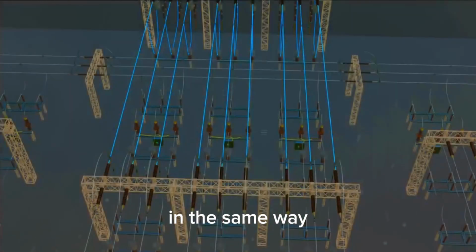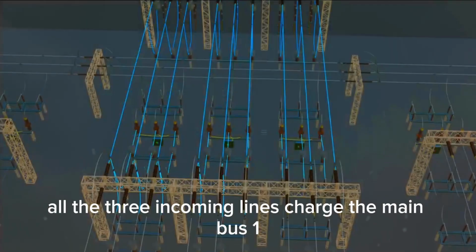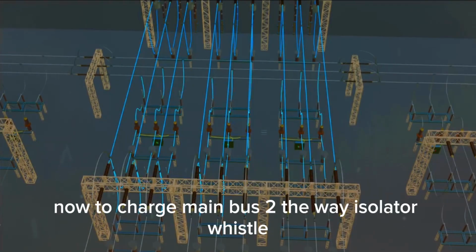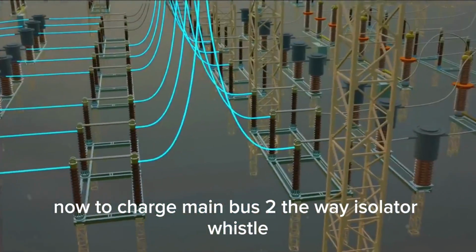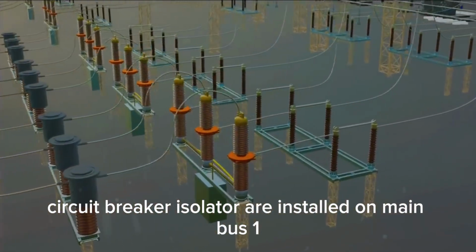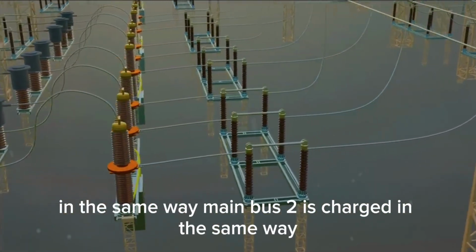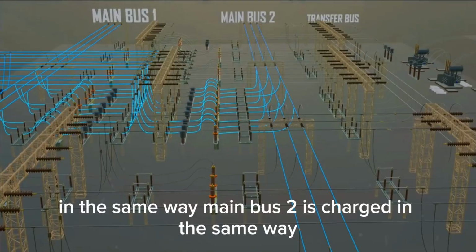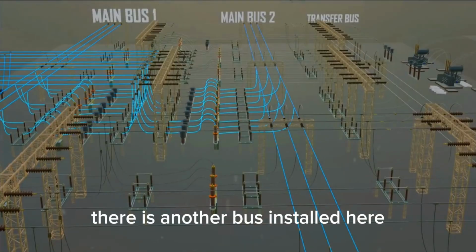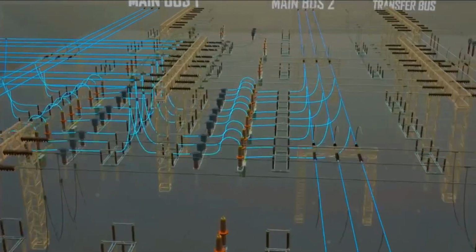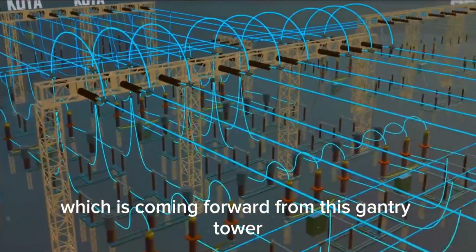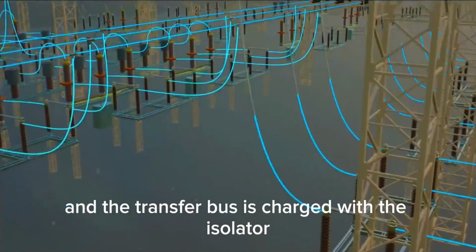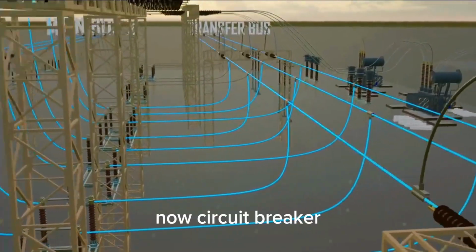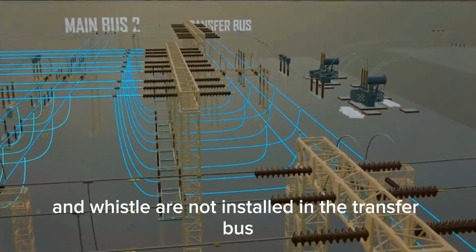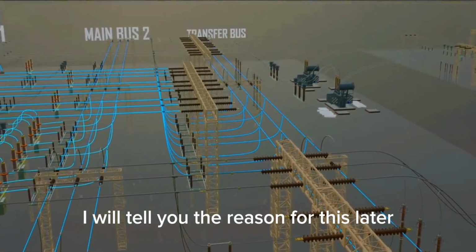In the same way, all the 3 incoming lines charge the main bus 1. Now to charge main bus 2, the way isolator, circuit breaker, isolator are installed on main bus 1, in the same way main bus 2 is charged. In the same way, there is another bus installed here which is called transfer bus. So the line which is coming forward from this gantry tower is brought down and the transfer bus is charged with the isolator. Now circuit breaker is not installed in the transfer bus. I will tell you the reason for this later.